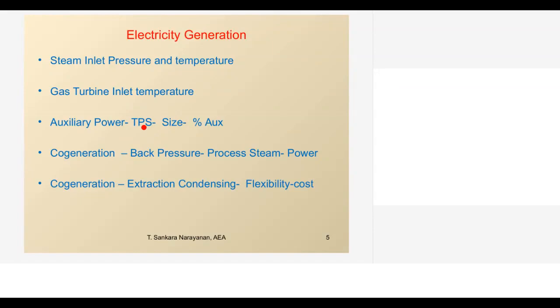Auxiliary power in a thermal power plant again changes based on the size of the plant, because in India we started with 110 megawatt, even 63 megawatt we are having. 63, 110, 210, 500 megawatt, 660 and up to 800. Today we are talking of supercritical boilers. So whenever we are going beyond 500 megawatt, the boiler feed water pump is changed to a steam driven pump. Then automatically auxiliary power will reduce by 2%. So why we are telling auxiliary power, these are all the design strategy made by the manufacturer of the power plant.